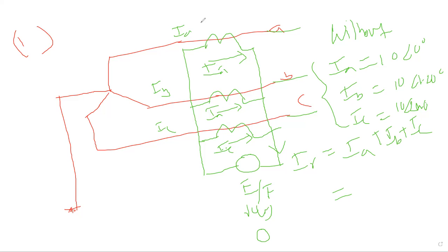So that is the thing. If there is no fault, that means all the phases are in perfectly balanced condition, right? Now, during this balanced condition, if you add all these phase currents, it will be 0. So as the resulting current is 0 during the healthy phase or without fault condition, this relay is not operating, right? Isn't it? Yes, sir.